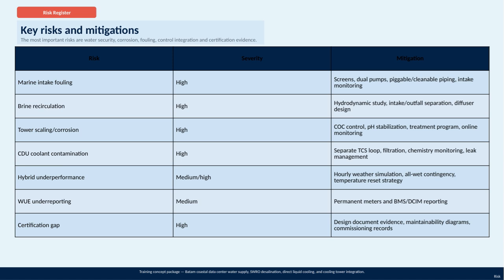clear and efficient. For brine recirculation, which is also a high risk, measures like hydrodynamic studies and careful intake and outfall separation using diffuser designs help minimize potential problems. When it comes to tower scaling and corrosion, we're controlling the cycle concentration, stabilizing pH levels, applying targeted treatment programs, and using online monitoring tools to detect issues early.